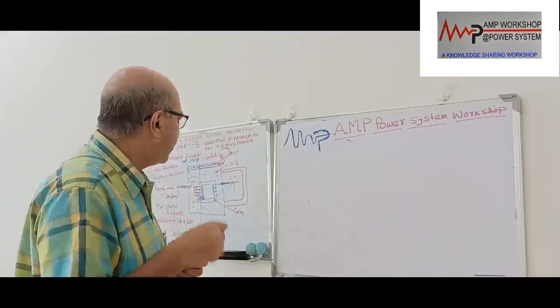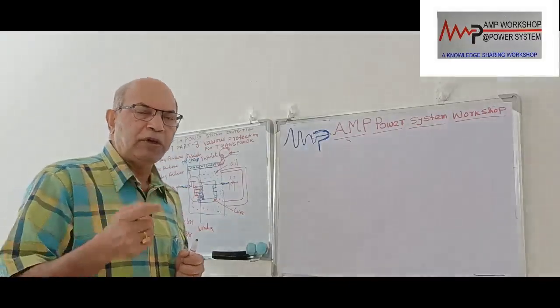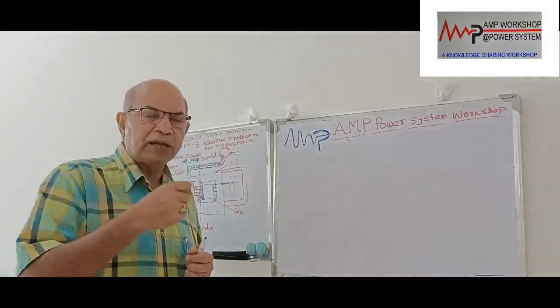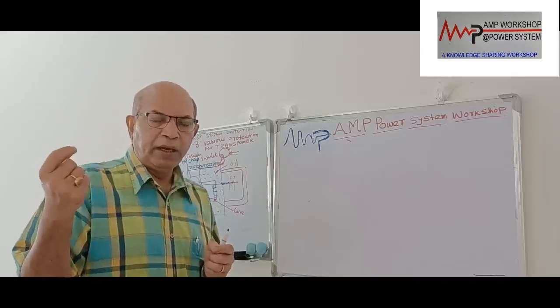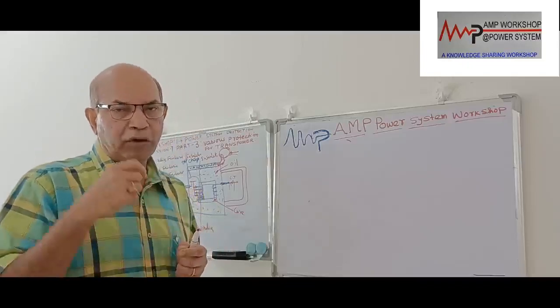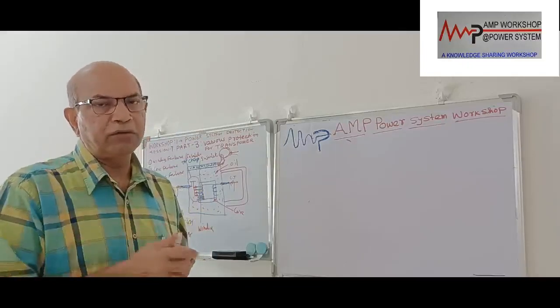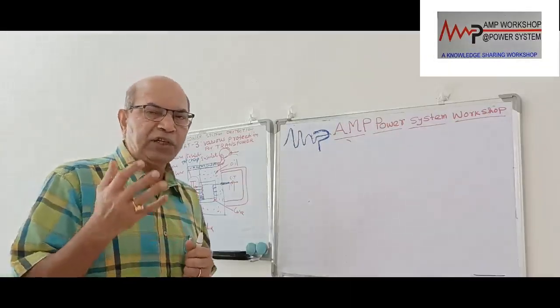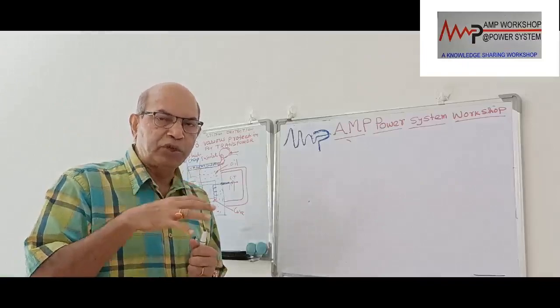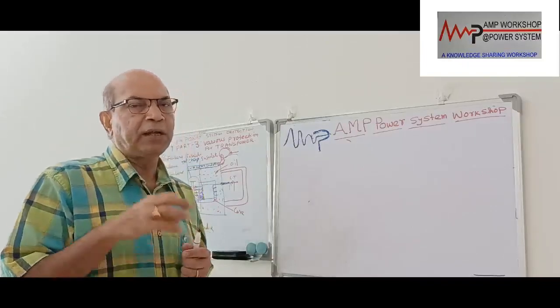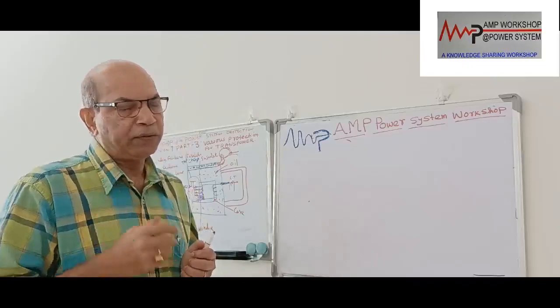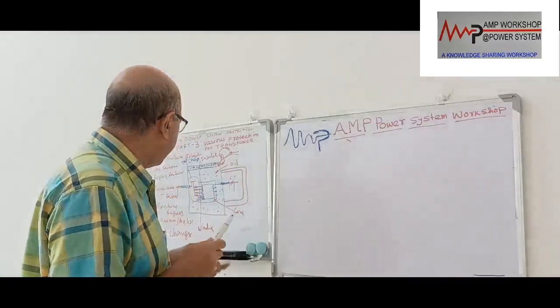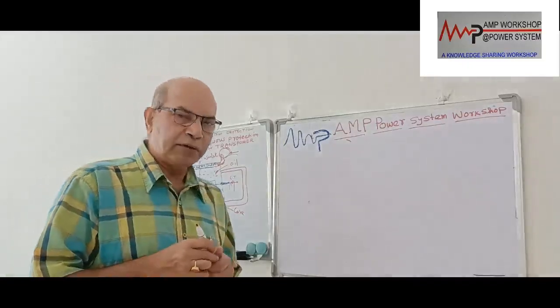There is also a possibility of leaking of fill gas, or the vacuum integrity could be lost, and that will also cause expansion of the transformer tank. Then the CTs mounted on the transformer bushing or inside the transformer tank may fail with time. So these are the various areas where failure can take place.